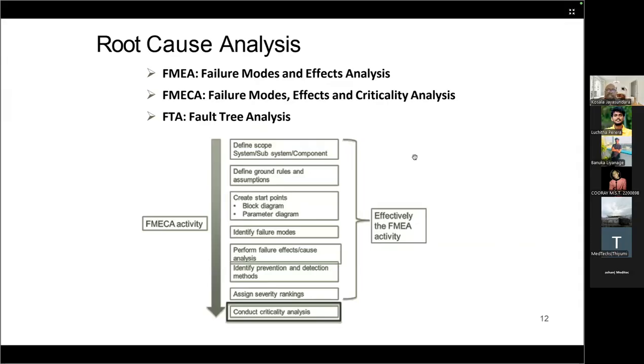So just to get an idea, the certification application document would be probably 15,000 pages altogether. The engineering development documentation alone will be 1,500 to 2,000 pages, but including all the test reports, third-party reports, everything, root cause analysis, that will be 10,000 to 15,000 pages, which is huge. That's why normally, even for a class 1 or class 2 product, you might need 2 full-time documentation people just to fill up all these documents, do the analysis, and present that to the FDA.